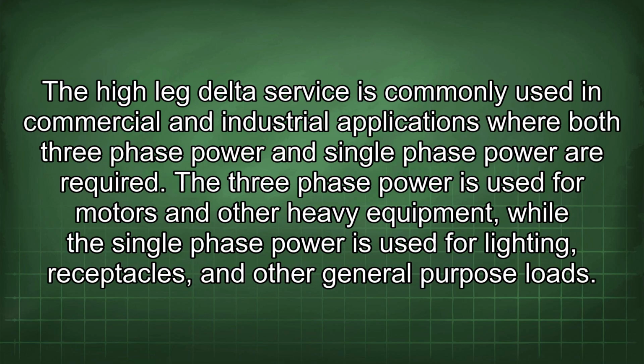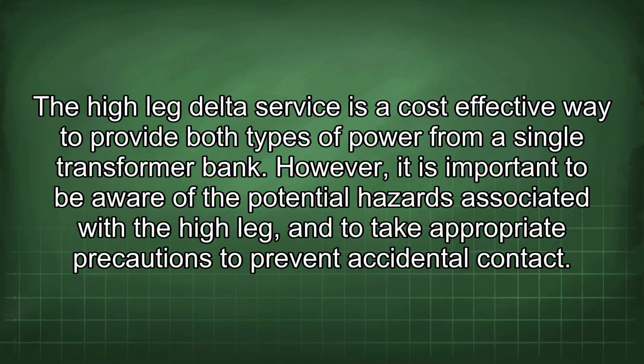The high leg delta service is commonly used in commercial and industrial applications where both three-phase power and single-phase power are required. The three-phase power is used for motors and other heavy equipment, while the single-phase power is used for lighting, receptacles, and other general-purpose loads. The high leg delta service is a cost-effective way to provide both types of power from a single transformer bank.